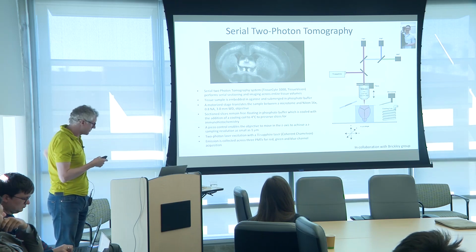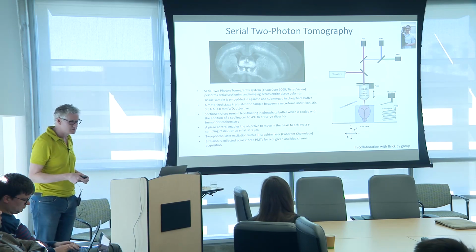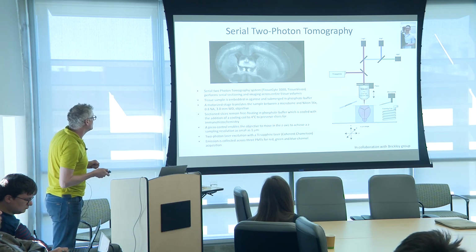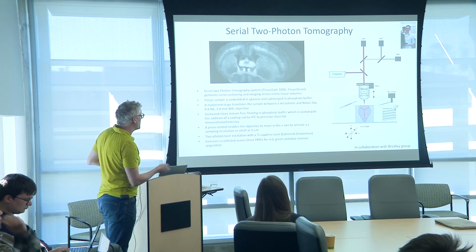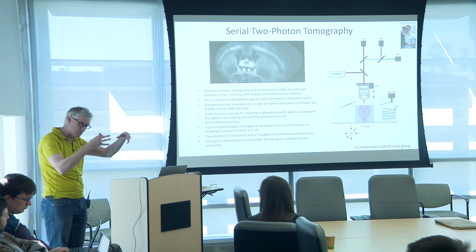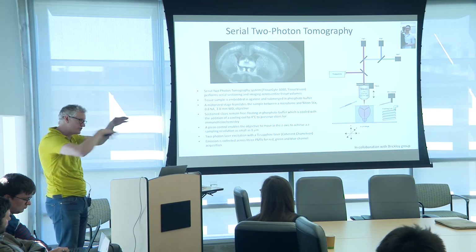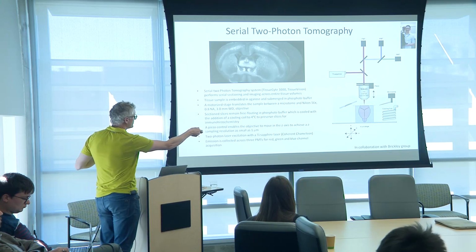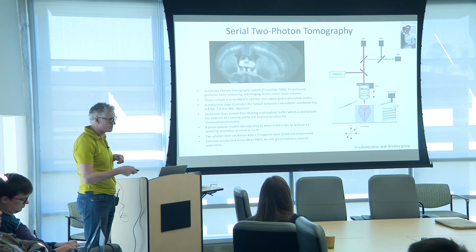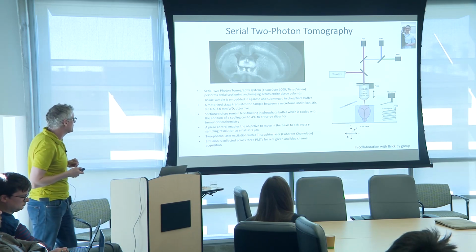So the next thing that we're doing is part of this pipeline. We do our in vivo experiment. At the end, we kill the mouse, take the brain out, and process it for serial 2-photon tomography. This is a TissueCyte system, and basically it images, say, a 100 micron thick section, tiled. So you take the whole mouse brain, mount it, tile imaging sections, image all of those, slice that off, image the next lot, etc. And then these slices float off in the bath. We found if you cool the bath, the slices sink to the bottom, which is much better. Otherwise, bits of tissue will float back over your sample and corrupt your imaging.